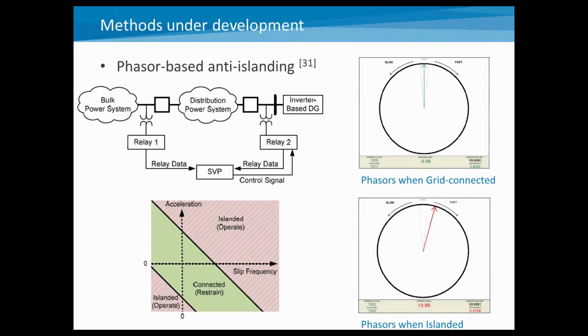An additional method that's underdeveloped is one that looks at the phasor measurements both at the distributed generation and at the bulk power grid, and basically uses phasors to understand if the islanded condition occurs. If they are interconnected, you'll have no phasor difference between the voltages on the system. As soon as you have an island, you'll probably have some drift there because of different load and DG requirements, and you'll start to see some kind of voltage differential, and that would allow you to detect this. Again, for this type of system, you will need some type of communication in addition to the phasor measurements.